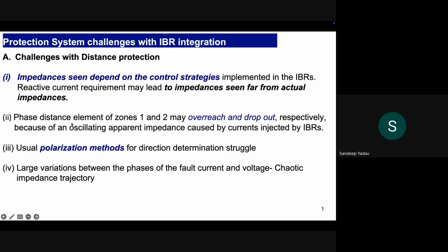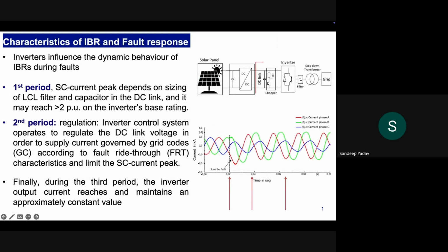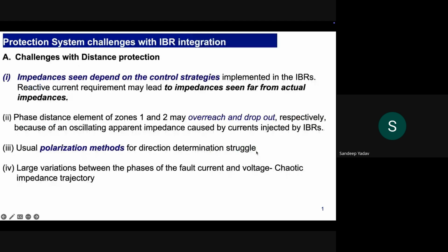So it may so happen, because as we saw in the last slide, the fault behavior, the current injection, is changing with time in the first period, second period, and the last period. The impedance seen by the phase distance element of distance relays may overreach or underreach or drop out totally because of the oscillating impedance seen by the relay.